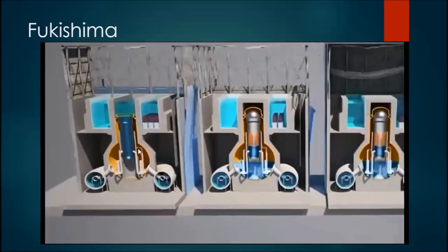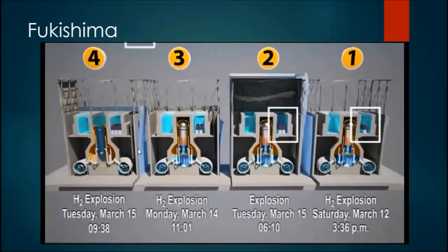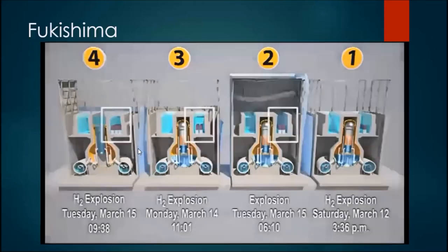The reactor's storage pools were also a great concern because they had lost their cooling systems, and in addition to this, they were not protected by any containment. Very little spent fuel was stored in Pool 1. However, there was much more in Pools 2, 3, and 4, especially Pool 4, which contained the equivalent of the 3 cores. In all 3 pools, the water started to boil, and without the help in extremis of cold water from helicopters and from a fire hose, the spent fuel would have caused considerable radioactive release into the environment.